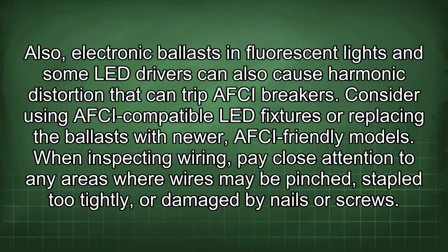Also, electronic ballasts, fluorescent lights, and some LED drivers can cause harmonic distortion that can trip AFCI breakers. Consider using AFCI-compatible LED fixtures or replacing the ballasts with newer, AFCI-friendly models.